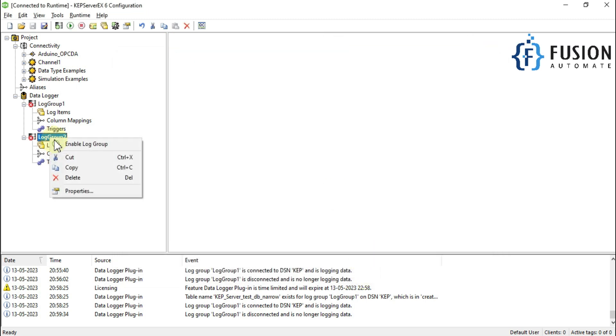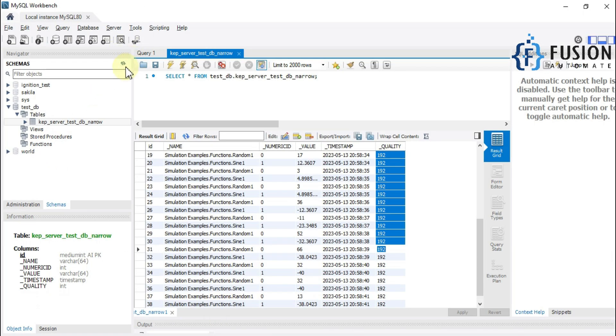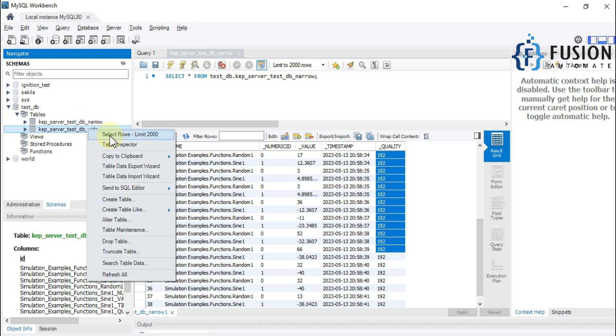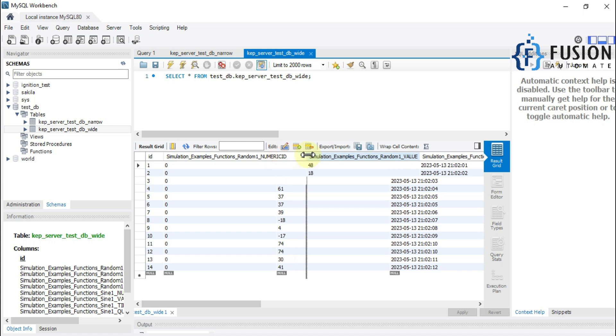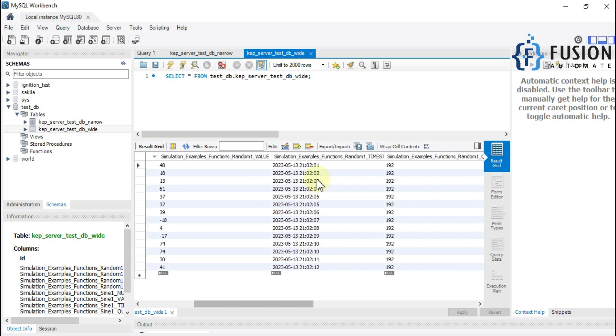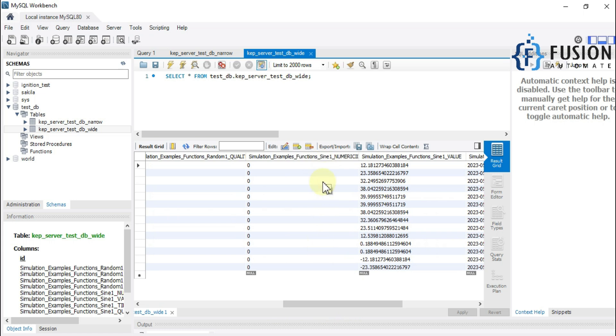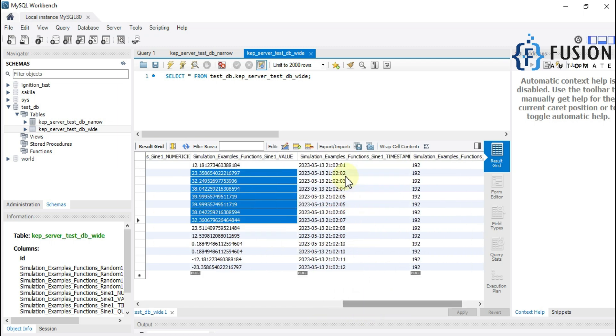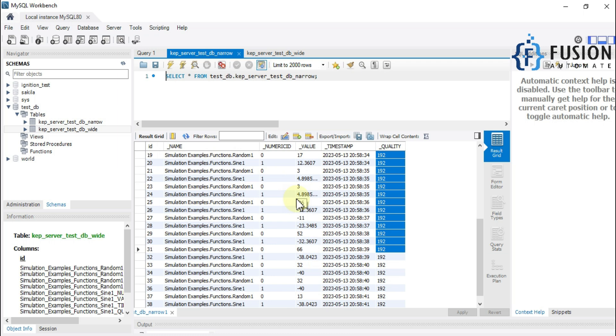Go to Trigger, set Always Trigger, stating interval 5000 milliseconds, log on data change yes. Press OK and start Log Group 2. You can see Log Group 2 is connected to DSN and logging data. Refreshing MySQL Workbench, there is now a second table. Selecting Top 200 Rows for the wide table, you can see it has separate columns: numeric ID for Sine, one column for Random, value of Random, timestamp of Random, quality of Random, then numeric ID of Sine.